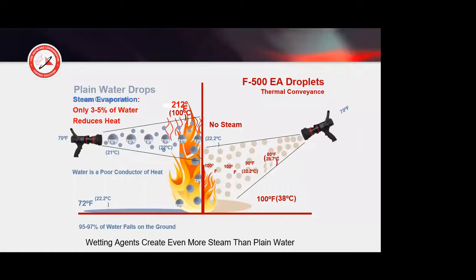So when you compare plain water versus the F500, what we see is, we come out of a nozzle, and it doesn't matter if this is a sprinkler head, an open head deluge, an IFI rotating nozzle, an HETV nozzle, or even a hand line, we come out at room temperature. In this case, we're using 70 degrees, and that water droplet is traveling towards the fire and towards the heat. What happens, like an onion, is the outer surface of that droplet heats up and converts to steam.